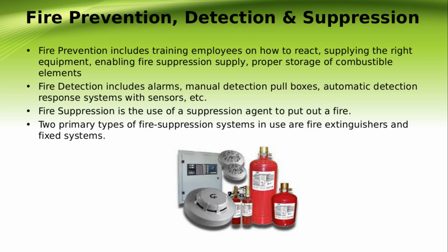Keep in mind, electronic equipment and water do not get along well. Fires that start outside electrical areas are well served by water-based sprinkler systems, but all these systems should have both manual activation and manual shut-off capability. You want to be able to turn off a sprinkler system to prevent potential water damage. Most systems are designed to activate only one head at a time. This works effectively to put out fires in the early stage.